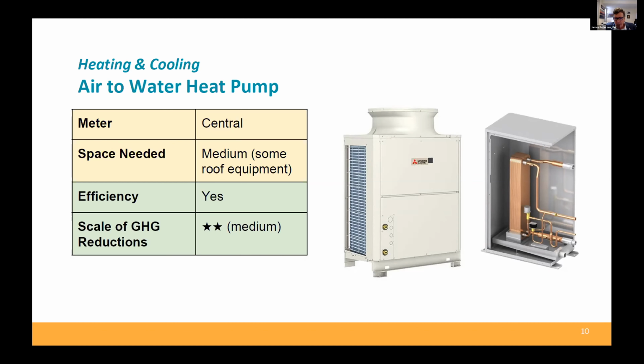So what we're doing here, with a goal of reducing refrigerant distribution in the building, is we've got this piece of equipment that's pretty generic looking on the right. But what we're doing is we're using a heat exchanger that's not far from the outdoor unit. So we have refrigerant piping that's very limited, connecting the outdoor unit to a heat exchanger that's just like it sounds. It's exchanging heat from refrigerant to water. And then the distribution from the heat exchanger through the building is water.